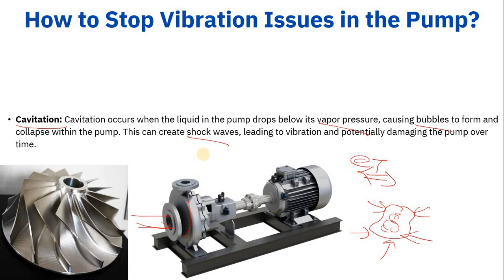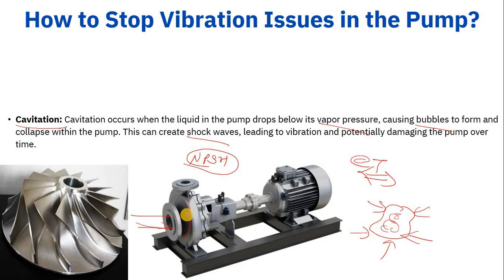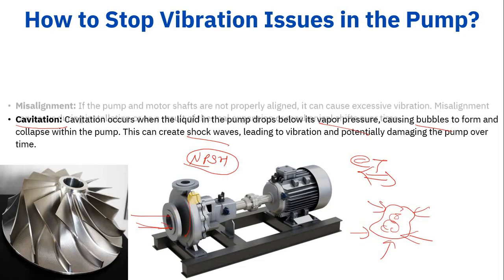To avoid cavitation, when we size the pump we ensure the NPSHA and NPSHR are properly accounted for. We also operate the pump above the vapor pressure, and we always perform priming to ensure there is no air locking.